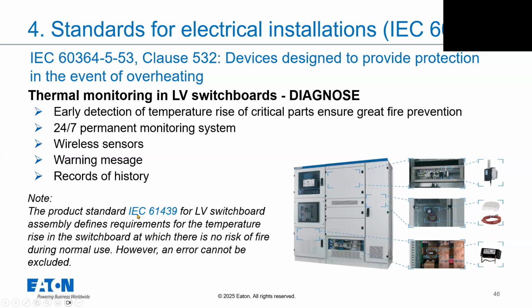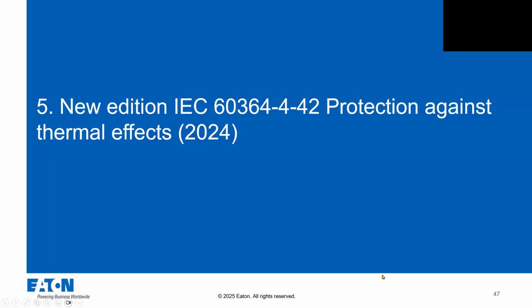we can also see in the standard for low voltage assemblies, standard IEC 61439, meaning for low voltage switchboards, a focus very strictly on temperature rise limits. If we use such a monitoring system, we can reduce risk to a minimum. It is really a recommended system for locations where we can't be sure that there will not be a problem with overheating and high temperature.